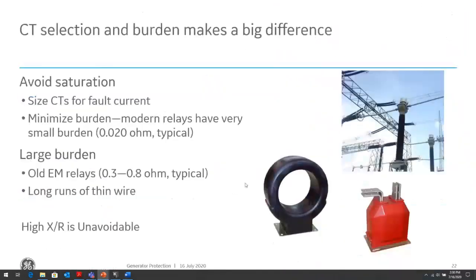The CT selection and burden make a big difference when we talk about CT saturation. When we size our CTs, we need to size them, to the best of our ability, to avoid saturation. So we need to size the CTs for maximum fault current level. We need to minimize the burden seen by the CTs, as CTs are rated for a certain excitation voltage across their winding. If we exceed that excitation voltage, we will push the CT into saturation. So the higher the burden on the CT, the quicker we will push that CT into saturation, because the larger excitation voltage it will see across its terminals.